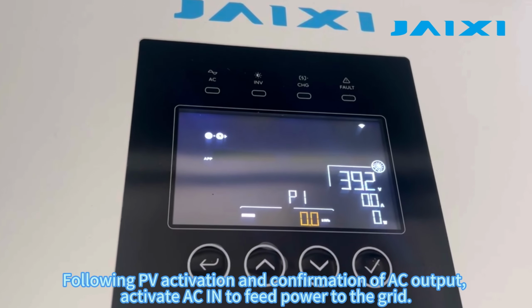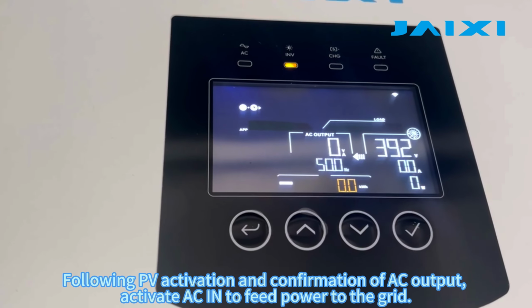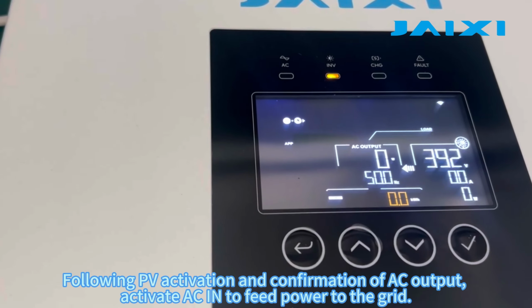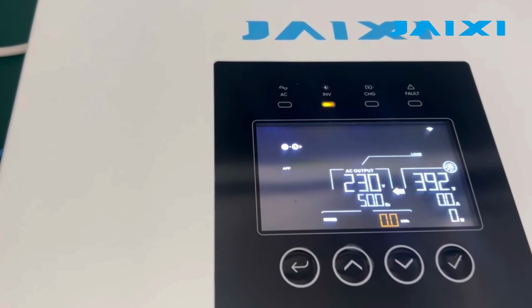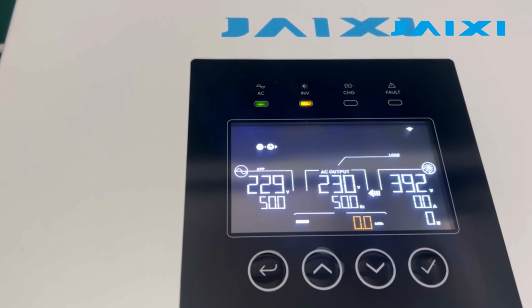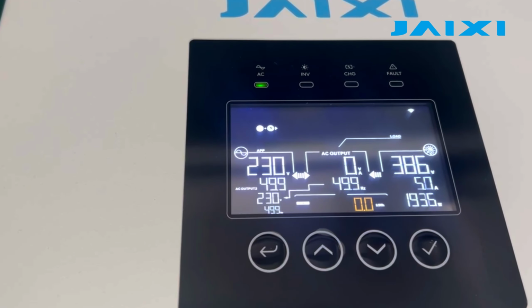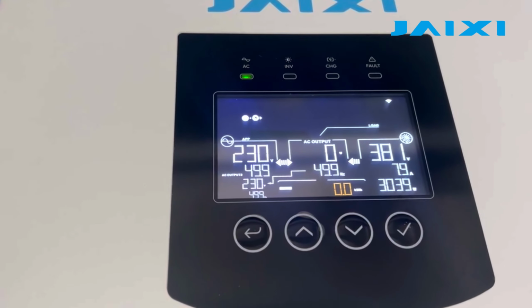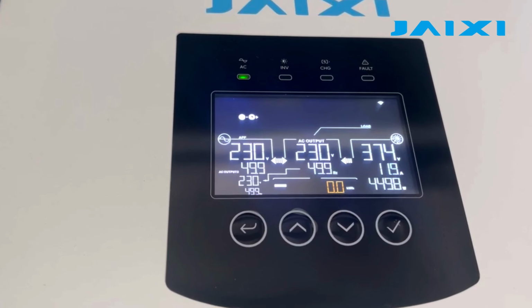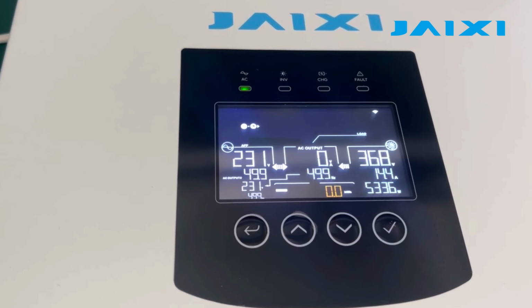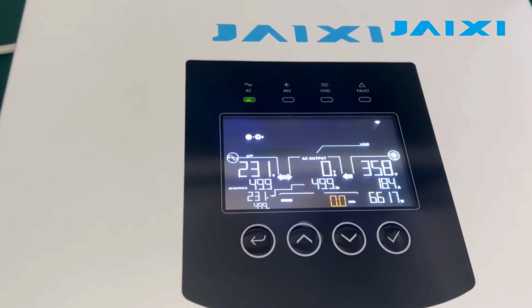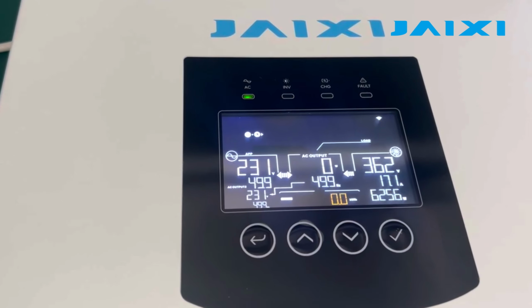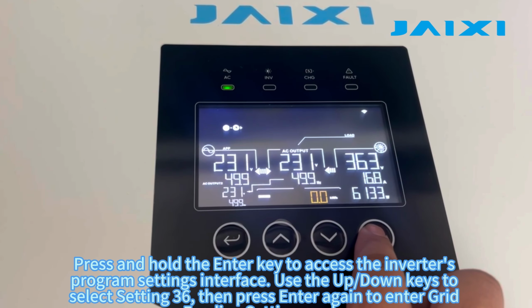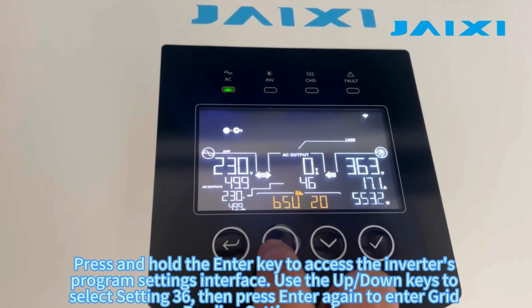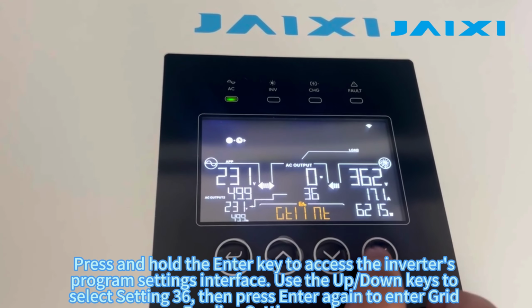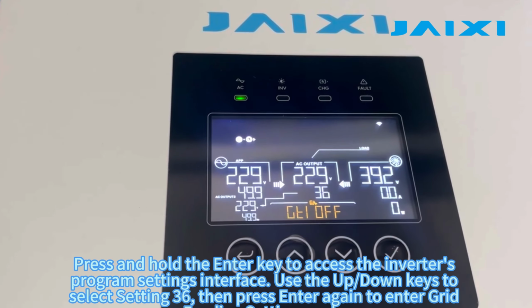Following PV activation and confirmation of AC output, activate AC in to feed power to the grid. Press and hold the Enter key to access the inverter's program settings interface. Use the up-down keys to select setting 36. Then press Enter again to enter grid feeding setting mode.